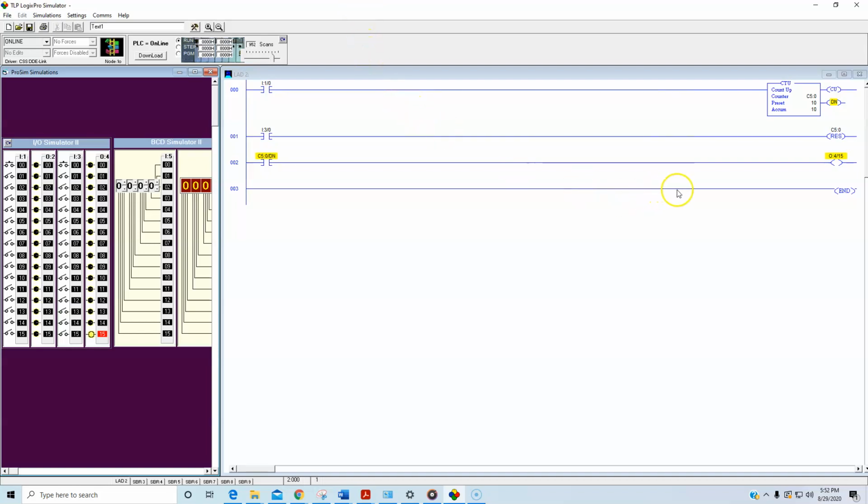For instance, if you've got a mechanical relay, that the manufacturer says that relay is good for 10,000 opens and closes. And those do have some values. I'm not exactly sure what the average is, but let's say it's 10,000. You could use a couple of cascading counters to count up to 10,000 and let you know where you could do some predictive maintenance on your relays by replacing them because they've reached their cycle count as far as number of open and closes of a mechanical contact.